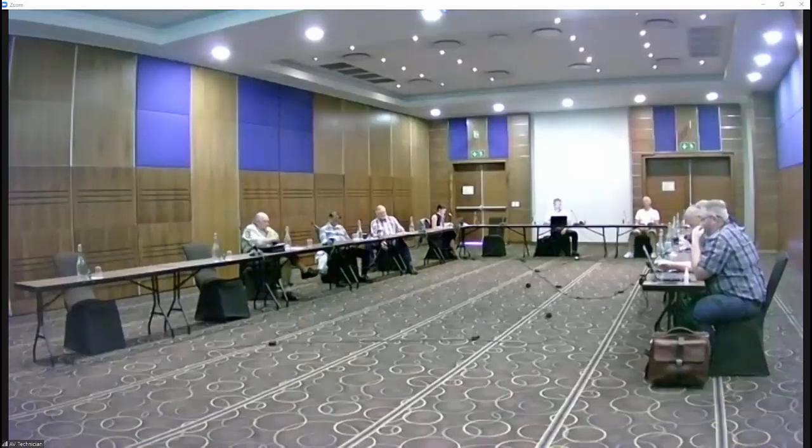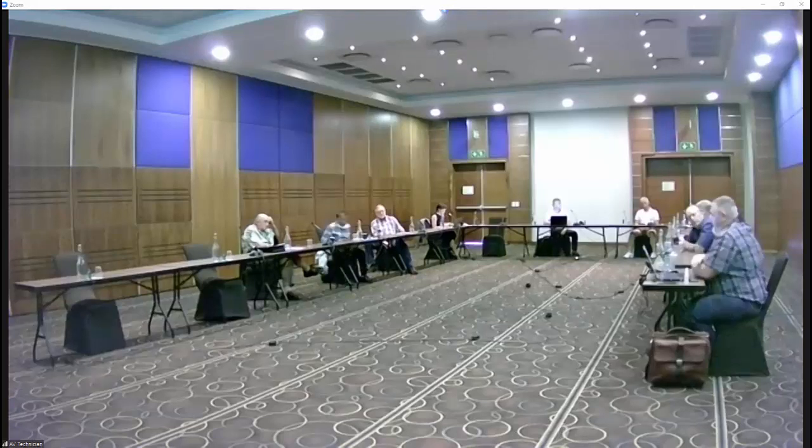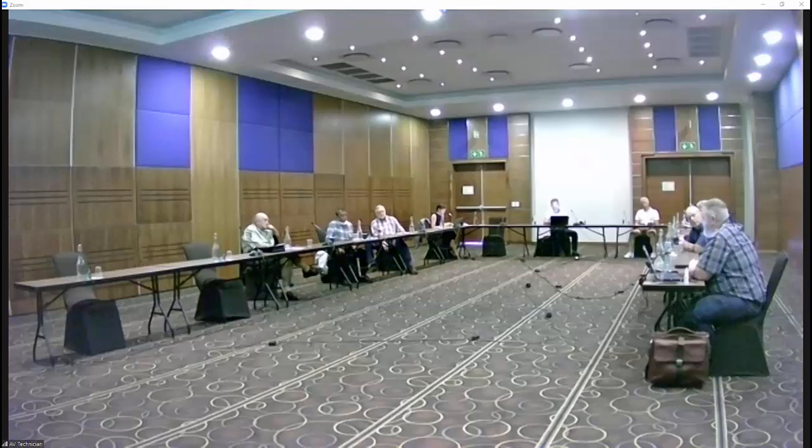So I can perhaps just give some comments on using natural ventilation. We've got a number of negative pressure ventilation rooms in Tygerberg Hospital, obviously, for the infection control of people that we admit with TB and so forth. When we do those assessments, they normally say 12 to 14 air changes per hour, and when we measure them, they come exactly to that, 12 to 14 air changes per hour.